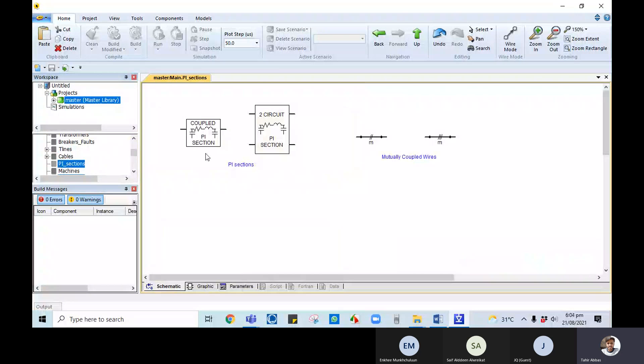If you are doing a transposition of a line, energization of a line, or insulation coordination, then we need to build the line correctly as per the parameters and tower structure. For that purpose, we get information regarding tower structures and conductor information, choose the appropriate model, obtain the line constants, and possibly perform a conversion of those constants, then use them in the pi section transmission line model.